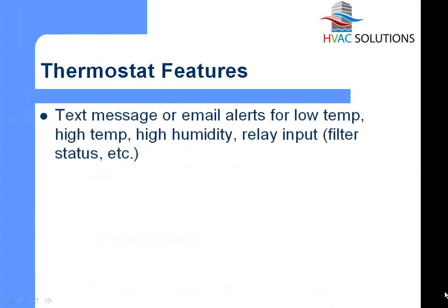All these thermostats have the ability to send alarms out. So if you connect them to the public internet, and obviously you wouldn't buy this stat if you weren't planning on doing that, you can have these thermostats send you an email or text message alert for low temp or high temp alarm. If you have a thermostat that has the humidity module option inside it, then it can also send you an alert for high humidity. And then if you have ones that have the relay inputs on them, then you can also have alarms related to those inputs. And if you have remote sensors for temperature, like a walk-in freezer, it can alarm you on stuff like that as well.